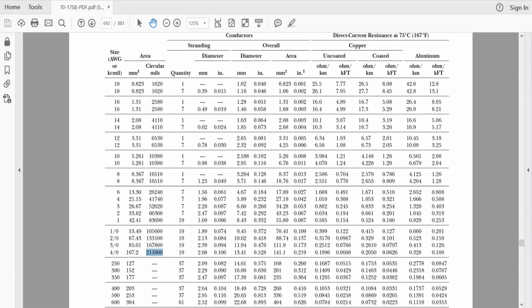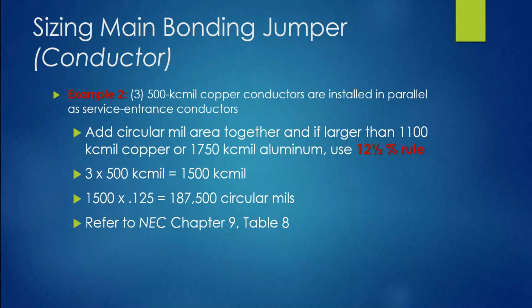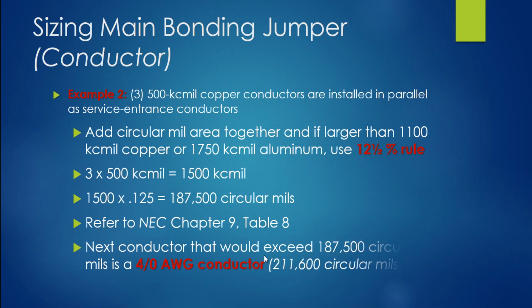All right. So let's go back to the presentation and see what our result was here. We know that we need to have a 4/0. And there you go. The next conductor that would exceed 187,500 circular mils is a 4/0 conductor. All right, so that's how we do that when we're sizing the main bonding jumper and we have a parallel application.